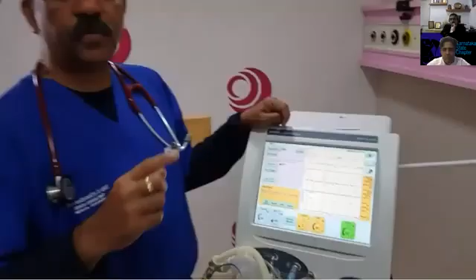So these are flow interrupter ventilators. In other modes, if the baby wants to breathe out when the ventilator is giving a breath, the baby will not be able to do so against that breath. Whereas on pressure support ventilation, if the baby wants to breathe out even when the ventilator is giving a breath, the ventilator will sense that and interrupt the flow at that level. That's why it is called the flow terminator or the flow interrupter. The pressure being given will be stopped and it will allow the baby to breathe.